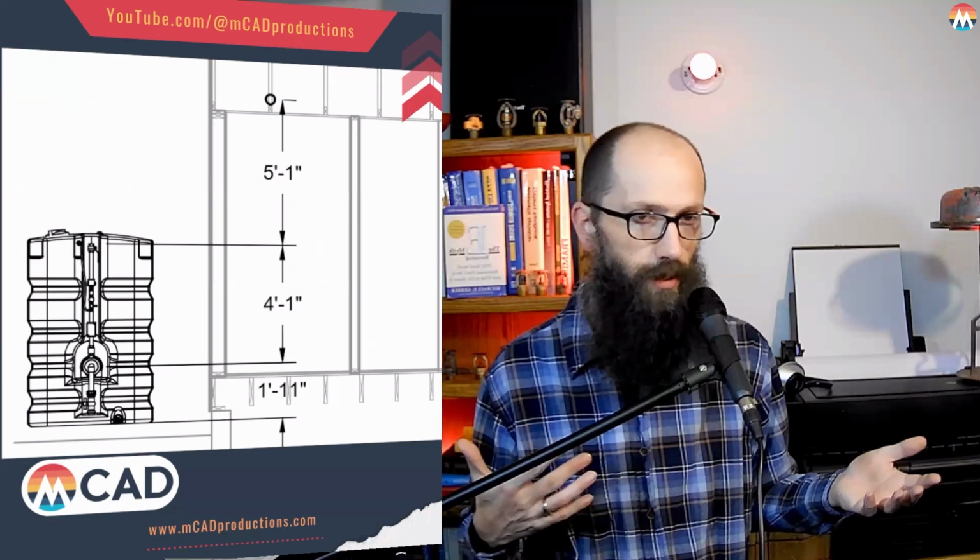So the negative 1 foot 11 it had in the calc, it's making up to that where the 4 foot 1 starts. That's my 0 point, and going up from there. And it's a little bit above the floor, which is normal. That makes sense because basically we usually come in, and after we come through the floor, we transition in pipe type. And so we usually need the node to be right there anyway.